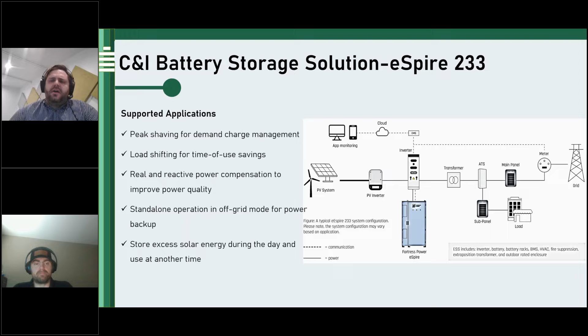It can be used and designed kind of like the solar design, where you have a transfer switch for the whole building ahead of either the main panel or the backup panel you're trying to protect, with just one input and output on the inverter. It's unlike the residential 48 volt inverters, where there's a grid input and a load panel output. This is a high voltage battery system with one input and output and a transfer switch ahead of it.